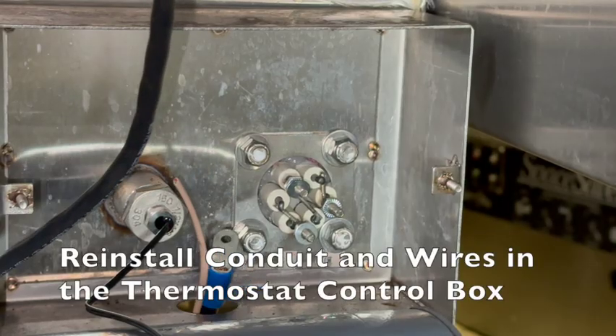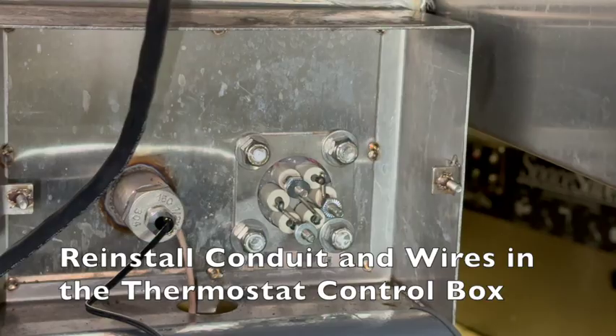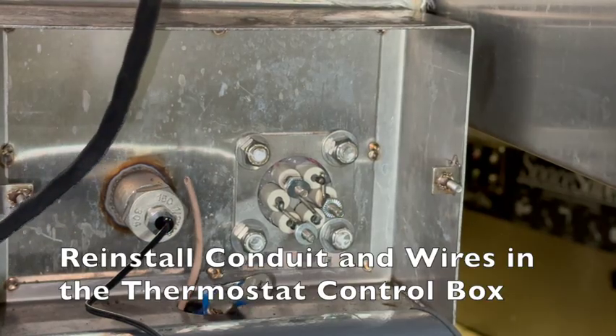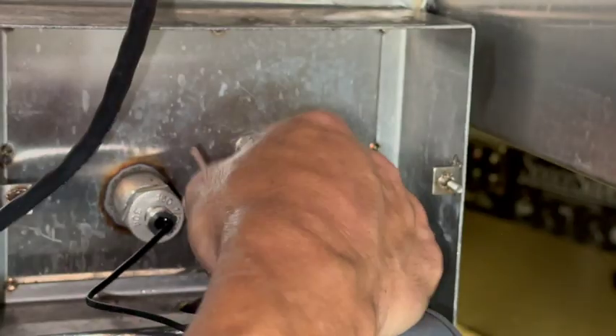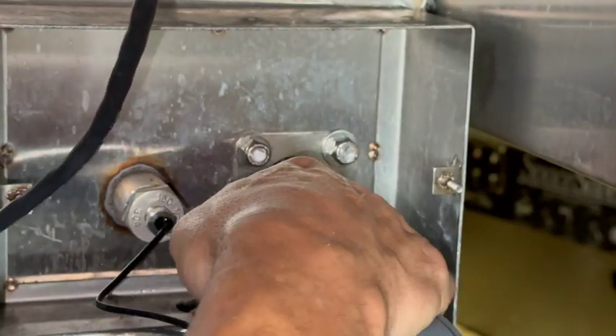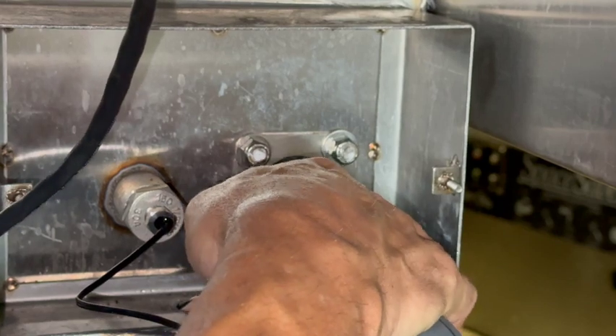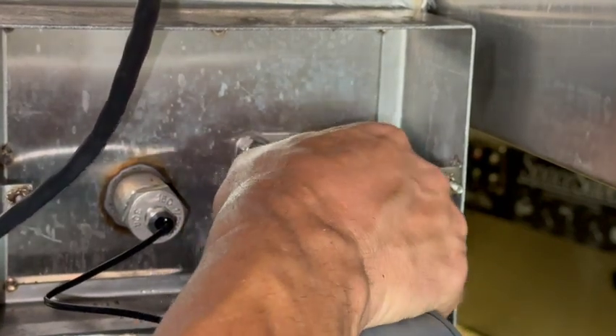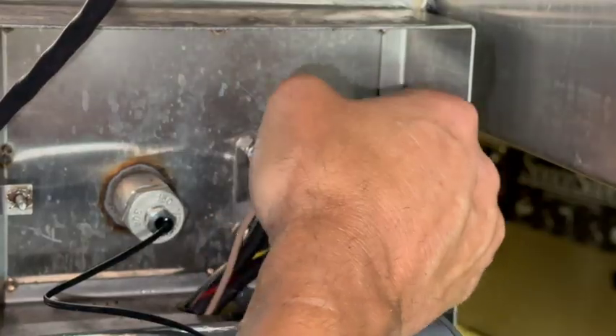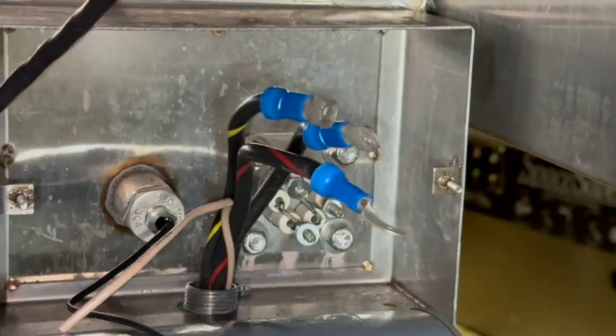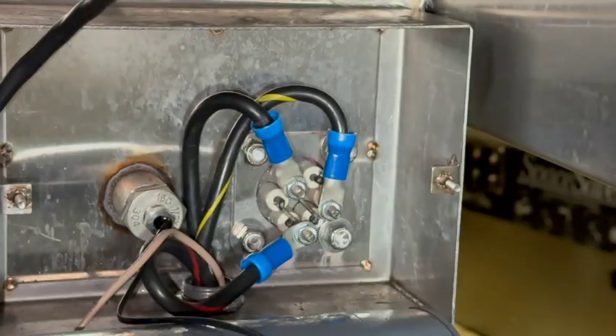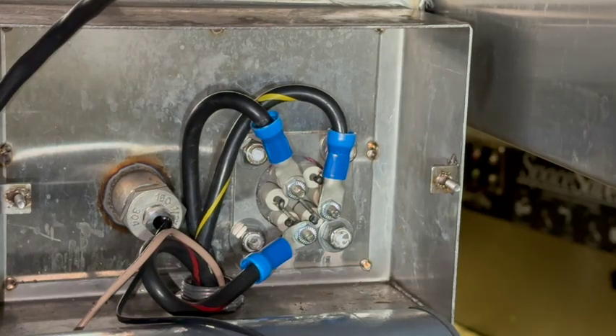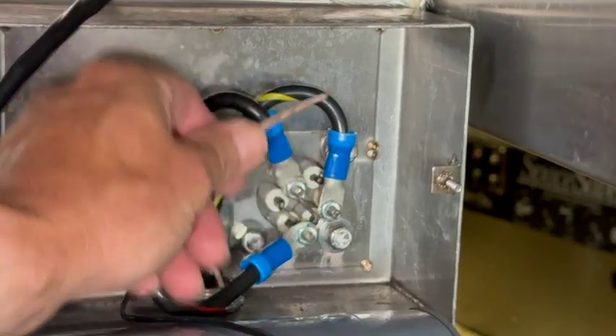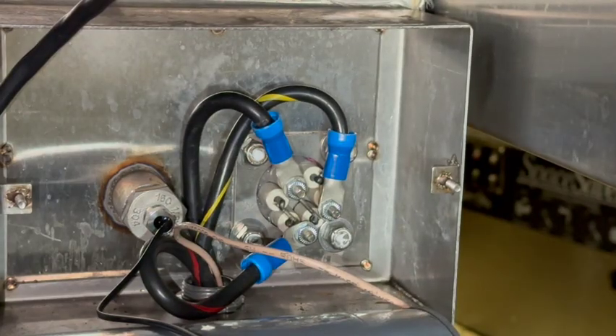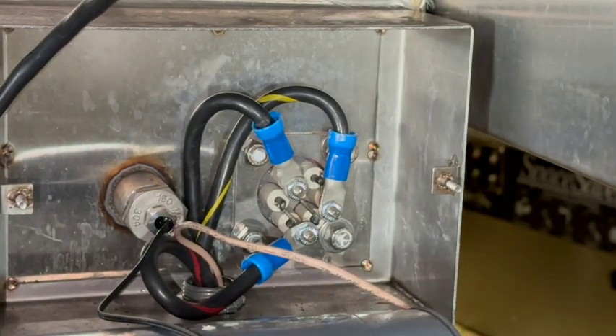It's pretty straightforward. But after I've got the probe wire through the conduit, now basically put everything back together. Like I said, this was probably the most labor intensive part of the whole install. Otherwise, it went pretty well. But this part here took the most time for sure. So again, you're just going to go back through and reconnect all your heating element wires. Make sure they're good and tight.